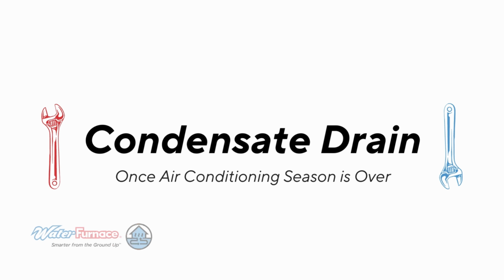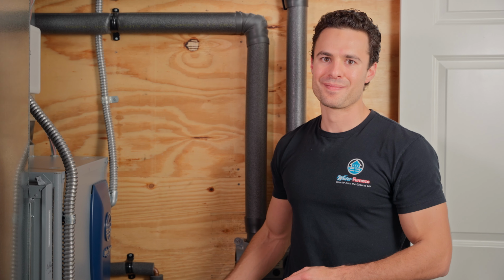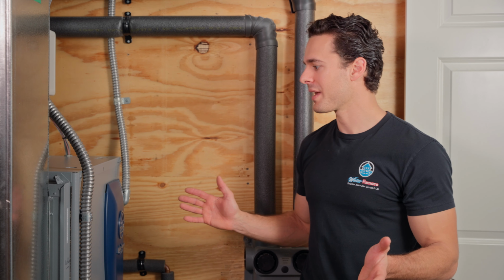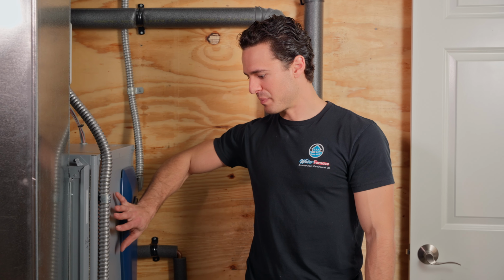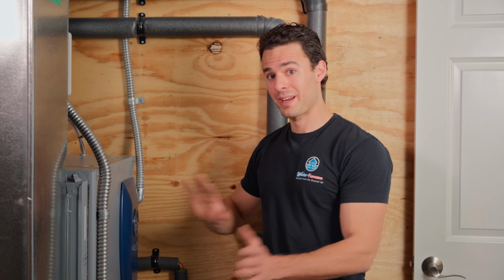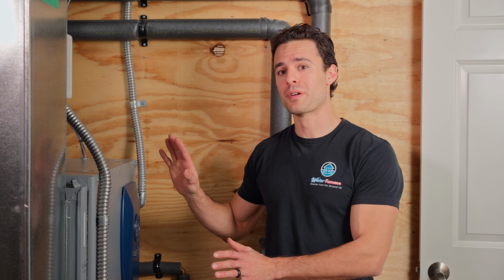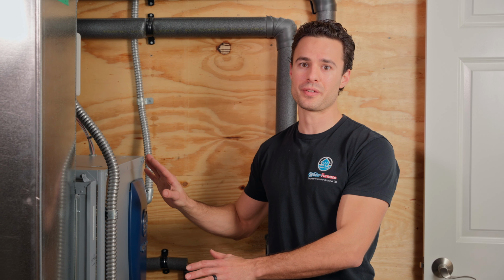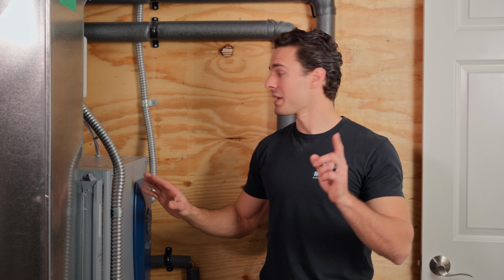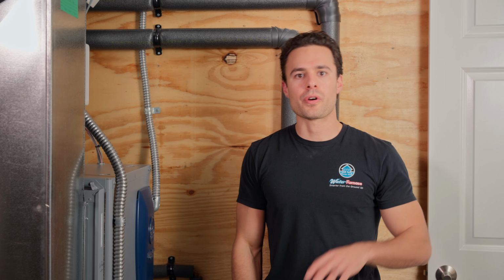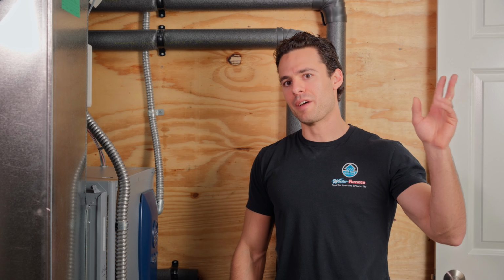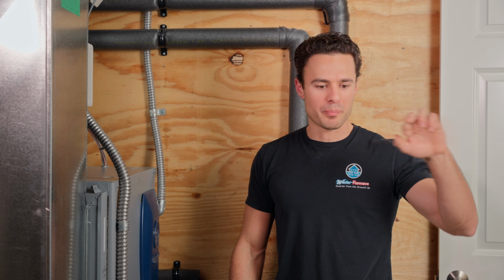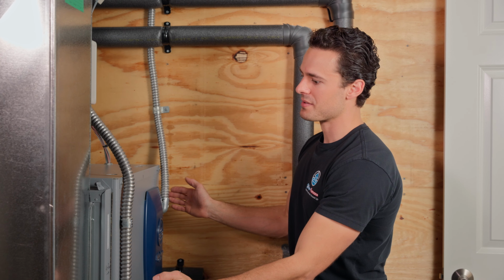So my other maintenance tip for you is make sure that your condensate drain is clear. And the way that we're gonna do that is by accessing this panel here. Now, before we get inside the cabinet, we wanna make sure that all of our power is shut off to the unit. And you're gonna do that probably either from a disconnect or from your main panel. You'll have two breakers. Flip both of those off as we have two power sources coming in.